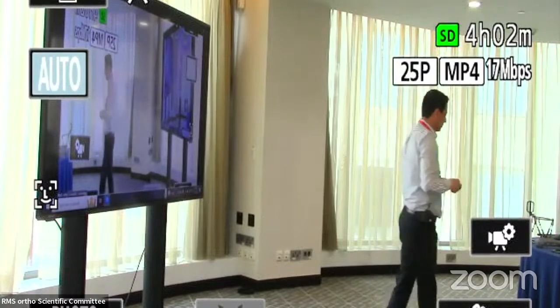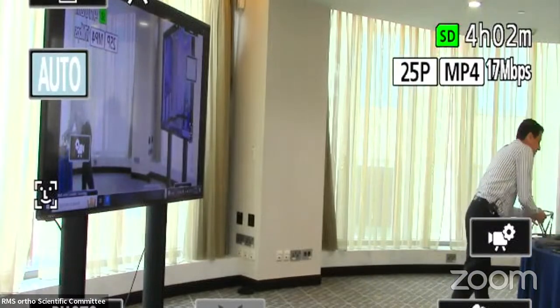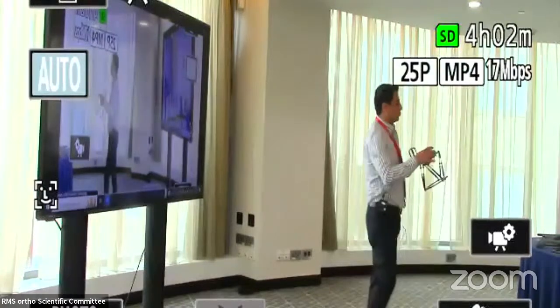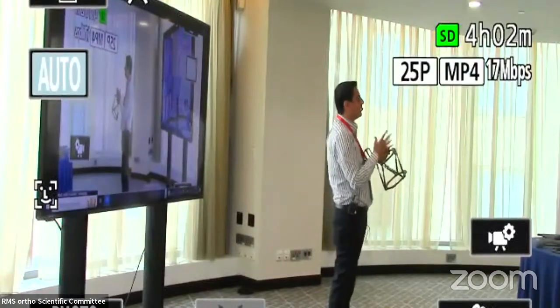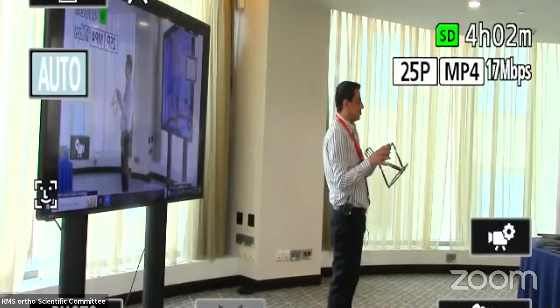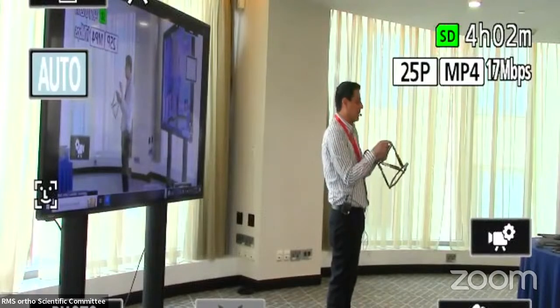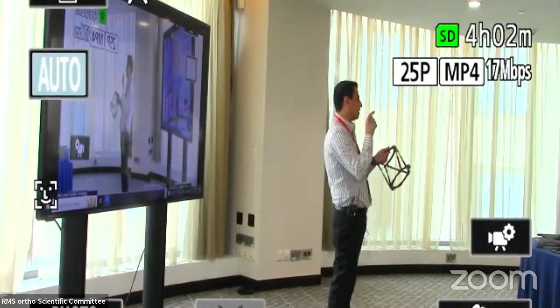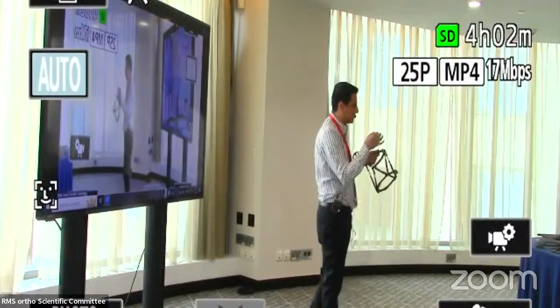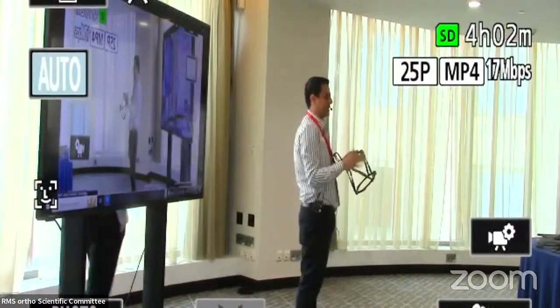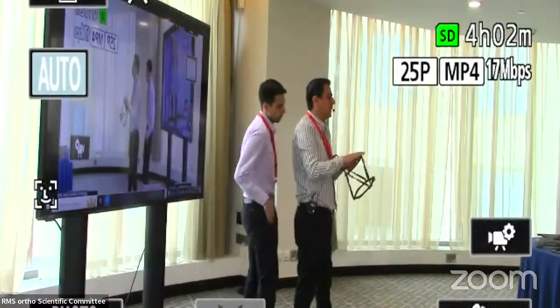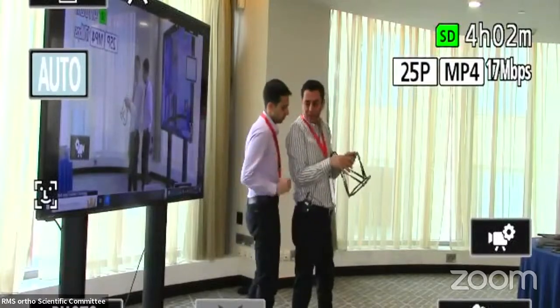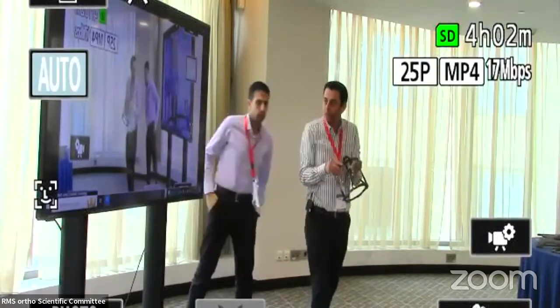Yes, exactly. Thank you. Because this device is connected to the computer, it will not understand where the frame is. You are telling it where the master tab is. For example, it is in the front of the tibia, exactly in the mechanical axis. This is what we are telling the computer when we enter the data.